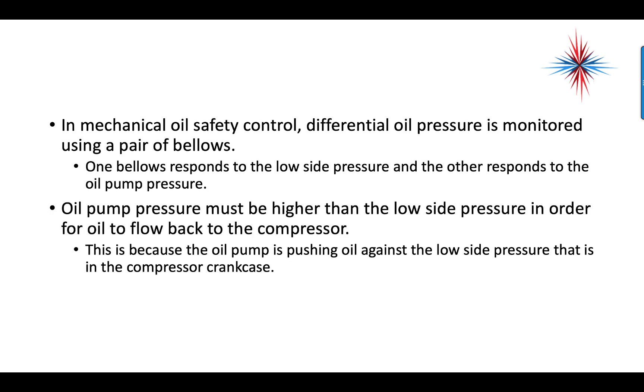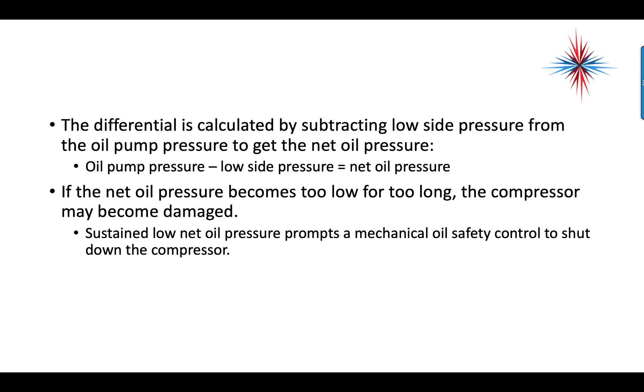In the mechanical oil safety control, differential oil pressure is monitored using a pair of bellows. One bellows responds to the low side pressure and the other responds to the oil pump pressure. Oil pump pressure must be higher than the low side pressure in order for oil to flow back into the compressor, because the oil pump is pushing oil against the low side pressure in the compressor crankcase. The differential is calculated by subtracting the low side pressure from the oil pump pressure to get the net oil pressure: oil pump pressure minus low side pressure equals net oil pressure. If the net oil pressure becomes too low for too long, the compressor may become damaged, and sustained low net oil pressure prompts the mechanical safety oil control to shut down the compressor.